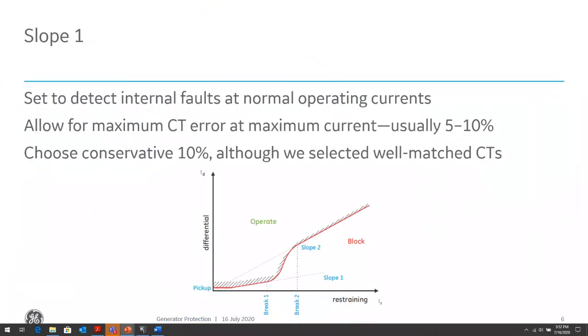The slope 1 is applicable for regions after breakpoint 1, so between breakpoint 1 and 2 and above the pickup. So it defines the ratio of differential to restraint above where the element operates. The slope is set to ensure sensitivity for internal faults at the nominal operating current levels. So this might be set to account for conditions such as CT inaccuracy, CT matching, relay inaccuracy, equipment inaccuracy, or issues caused by maybe DC offsets, because any CT could saturate at any point with DC offset. So if you have a case where you will see high DC offset, you might want to adjust the slope.